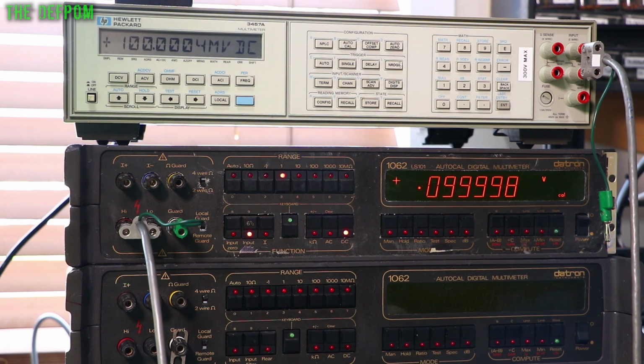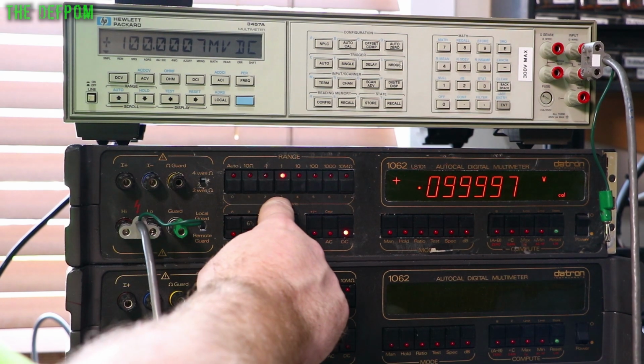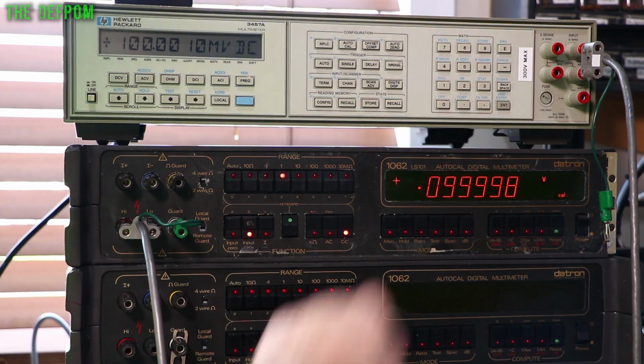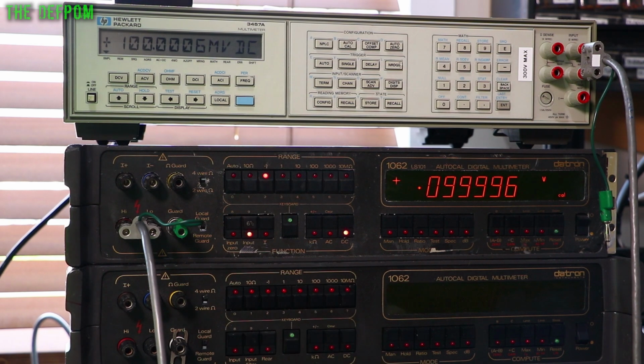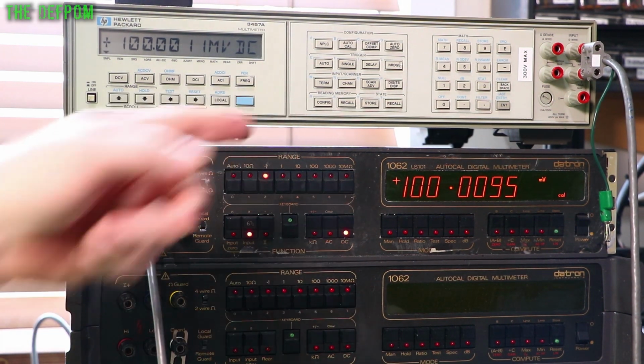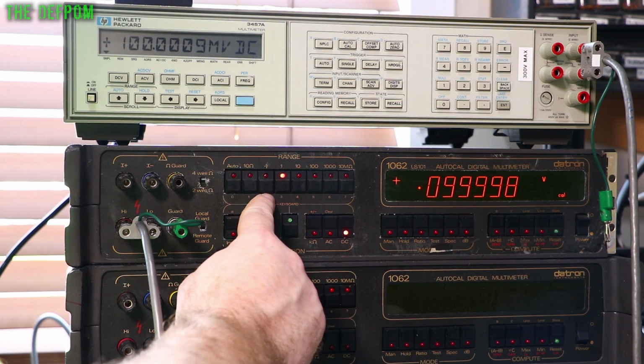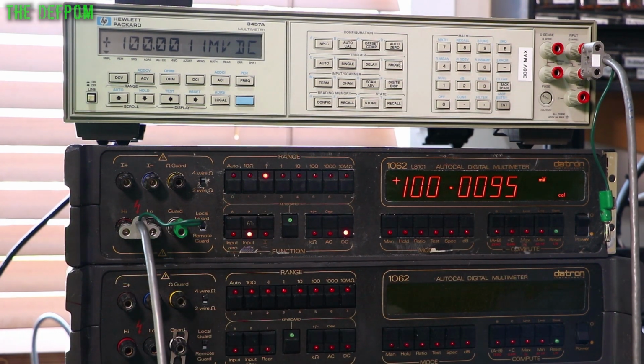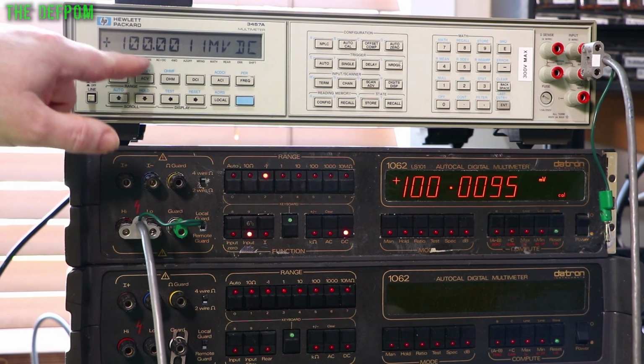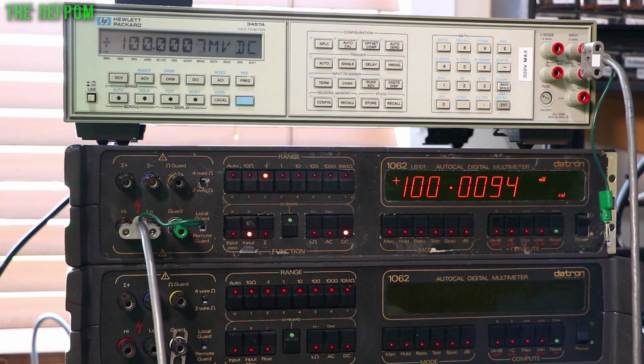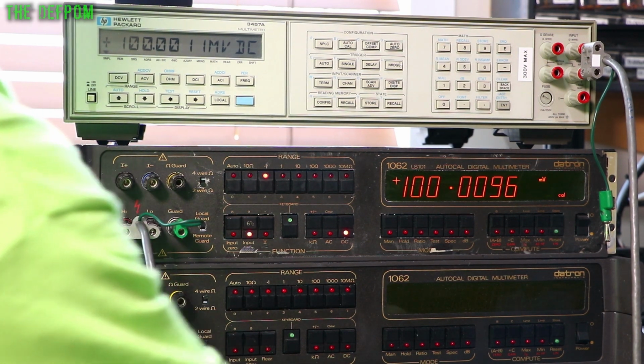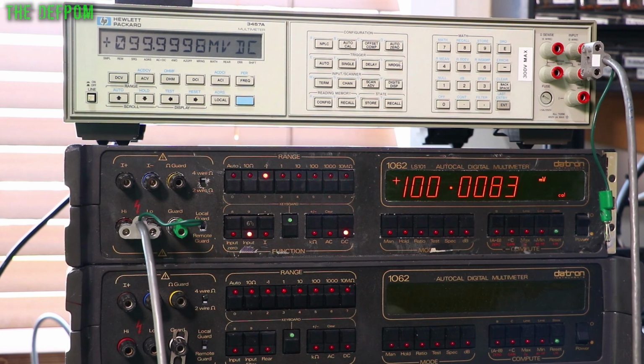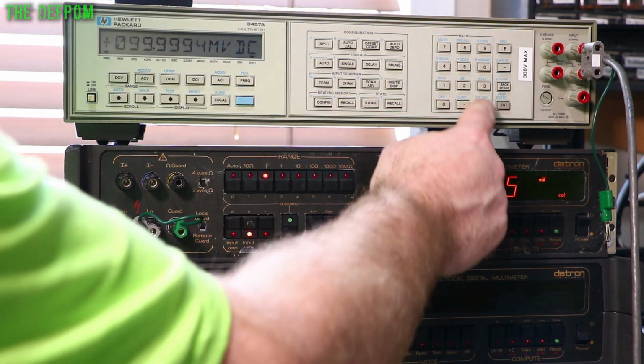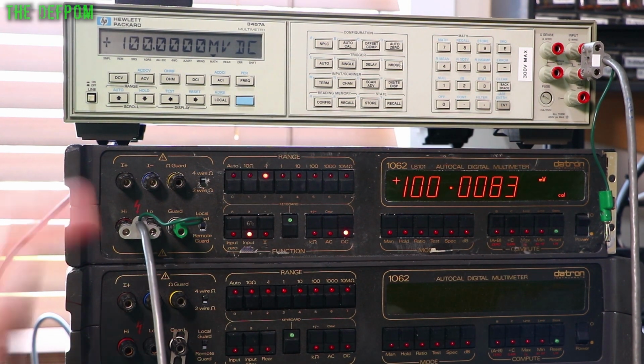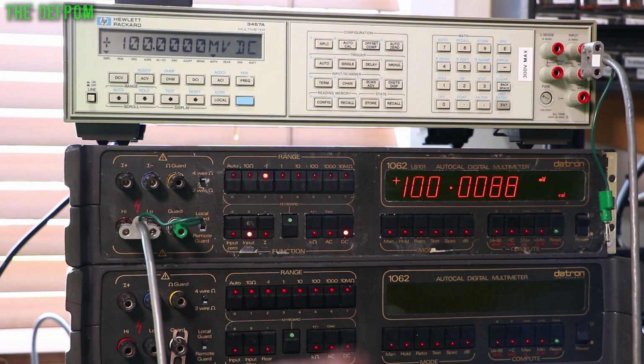So now I've got to do the same thing for the 0.1 volt range. I'm still in 1 volt range right now. See, it's looking pretty close. It's 100 millivolts, obviously. And you can see there's a difference between those two ranges. Okay, so this one's looking closer than this one. So you can see up here on the HP what we're actually getting at the calibrator. I don't have filtering turned on, so it's, you know, real time. I mean, this is probably closer there, that particular point there. If I turn the filter on, we'll see what we get. Right, so it's looking pretty good there, pretty much exactly right. So we'll set this one to that.